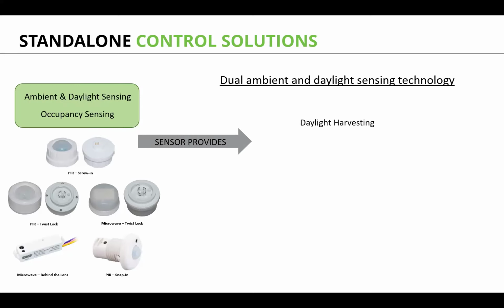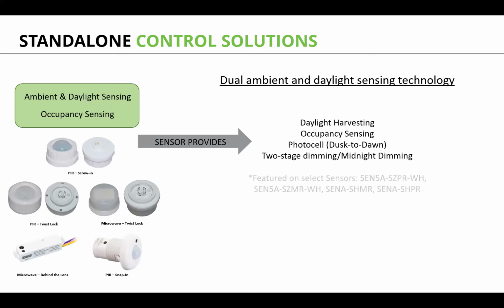All of these sensors feature daylight harvesting, occupancy sensing, a traditional photo cell if you want it to act that way, 2-stage dimming, and midnight dimming, which basically means once the sensor turns on at night, it will stay on for maybe 6 or 8 hours, and then dim down or shut off entirely. At midnight, do you really need the lights at full brightness? Probably not. So that's the concept: the fixtures turn on, say at 5pm, stay on for 6 or 8 hours as programmed, then dim down or shut off entirely.